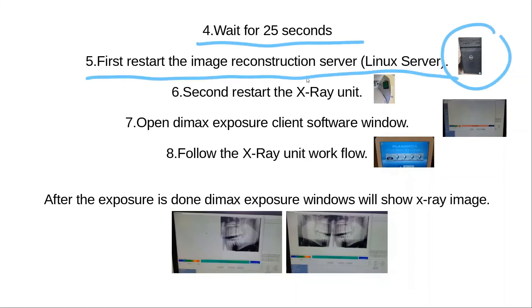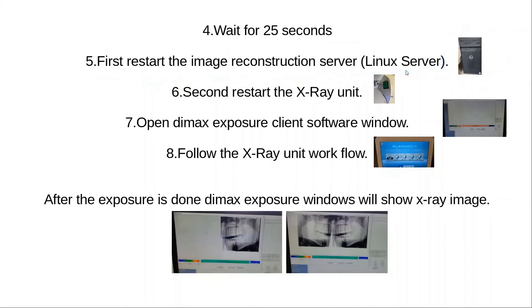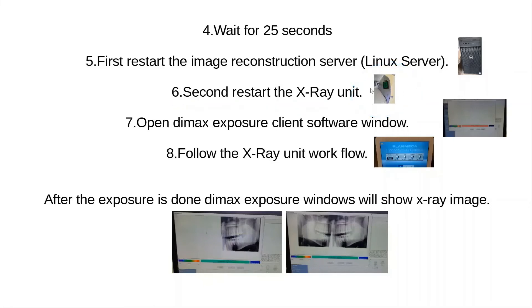Once done, move on to step 5: restart your image reconstruction server by pressing the power button. After that, move on to step 6: restart your X-ray unit by pressing its power button.